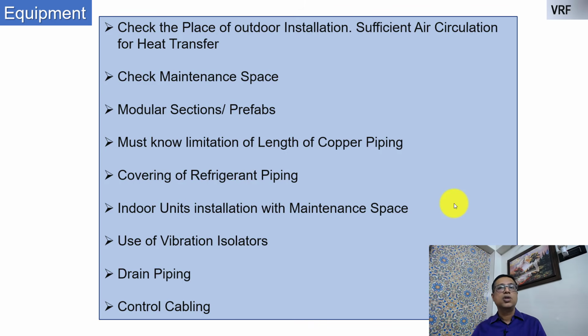You must also know the limitations of copper piping in terms of length and vertical height, right? Covering of copper piping, because mostly it is insulated, is very important, because otherwise there is an impact of UV. Also, there are impacts because of physical damage that we need to look at. The indoor unit also needs to be installed with proper maintenance space. A vibration isolator needs to be used. Proper drain piping needs to be done.